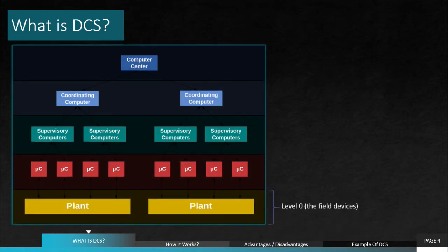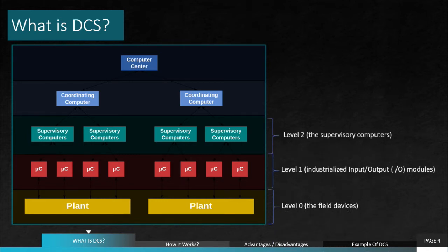The first level is level 0. Level 0 will contain field devices such as flow and temperature sensors, and final control elements such as control valves. Next is level 1. It contains industrialized input-output I/O modules and their associated distributed electronic processors. Next will be level 2, which contains the supervisory computers, which collect information from processor nodes on the system and provide the operator control screen.